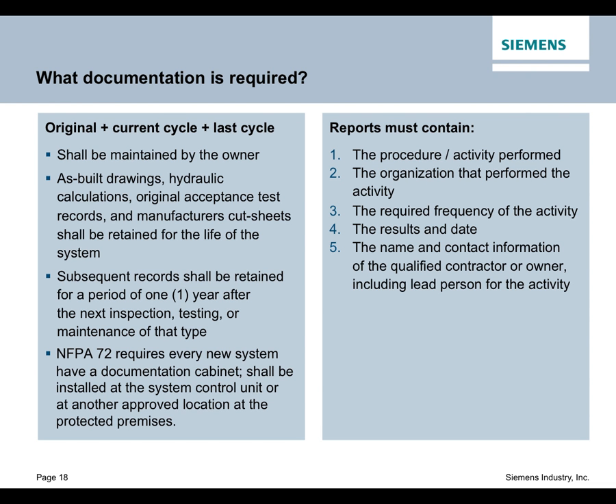And on the right-hand side, you can see what the report must contain, and that's all pretty basic information out of the code. But if I were to make a recommendation that may be considered above and beyond the code, it is to do the best you can to keep this data electronically, and I would keep it for as long as you possibly can. If an event, a fire, anything serious should ever occur in your building, the more positive documentation you have that shows you did your due diligence, that you were proactive in your fire safety management, that you have 10 years' worth of records that show your system's performance and maybe a few deviations and a few repairs, that will be of great value to you overall in the big picture of things.